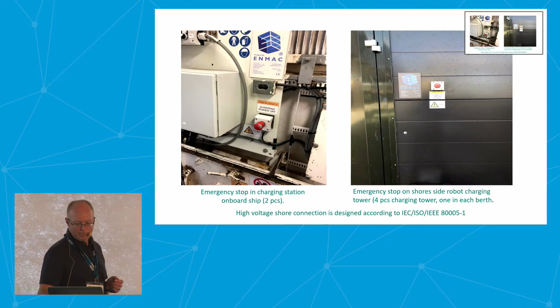One other thing that is also very important is the quality of the cooling water. As I said before, it's water-cooled modules, and here we have a pre-filter of the deionized water, and then a UV filter. You also have to keep control of the conductivity of the water, which is measured all the time, and it should not be above 100 microsiemens. It's adjusted with this mineral filter here.